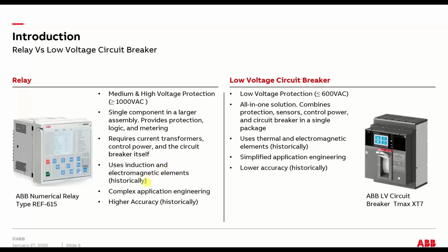A relaying system requires a bunch of engineering, obviously, because you have multiple components and they all have to work together as a system. And it's the responsibility of the specifying engineer and design engineer to make sure that the relay, the CTs and the breaker are all working together as a system, and to know what the totality of those components can do performance-wise. Whereas for the low voltage breaker, it's printed in a data sheet exactly what that breaker can do in terms of its curve. The curve includes all the trip and total clear times, and so it's a package versus a system.